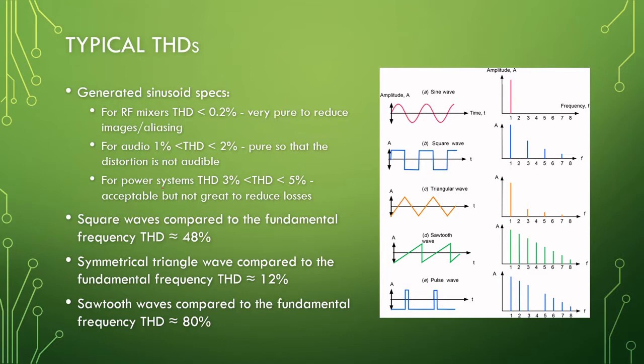For power systems, when you're driving something with a sinusoid, three to five percent maximum, or else you will have losses in your system. You will have power dissipated elsewhere where you don't want it dissipated.